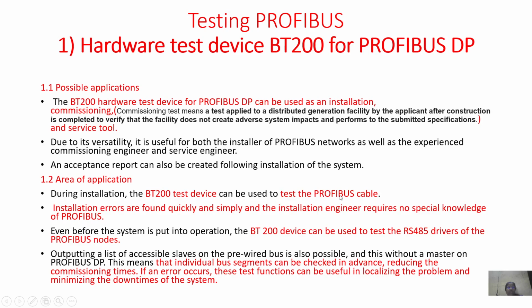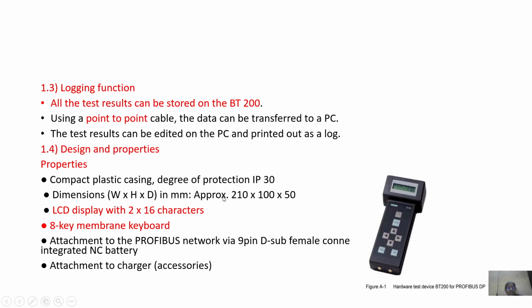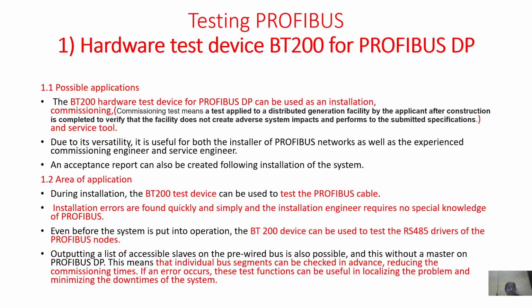So that is the BT200 hardware test device for Profibus DP, which can be used as an installation, commissioning, and service tool. Due to its versatility, it is useful for both installers of Profibus networks as well as experienced commissioning engineers and service engineers. So the area of application: it can be used to test the Profibus cable.